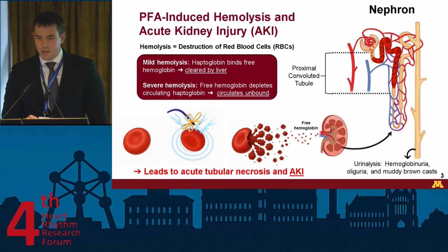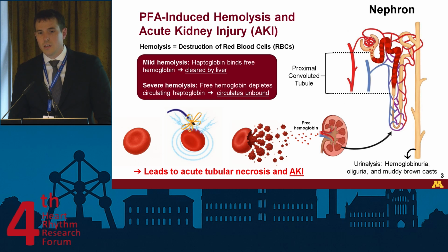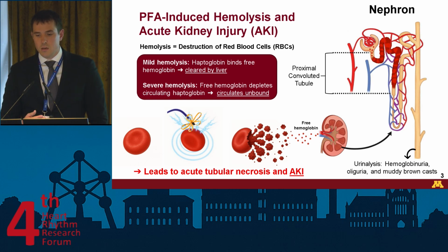So you have a red blood cell that passes in the heart where an ablation is occurring. And during that ablation, there's a pulse electric field. That red blood cell passes through that electric field, and if it reaches a specific threshold, then it causes hemolysis. And in more severe instances, like I mentioned, the circulating haptoglobin is depleted.